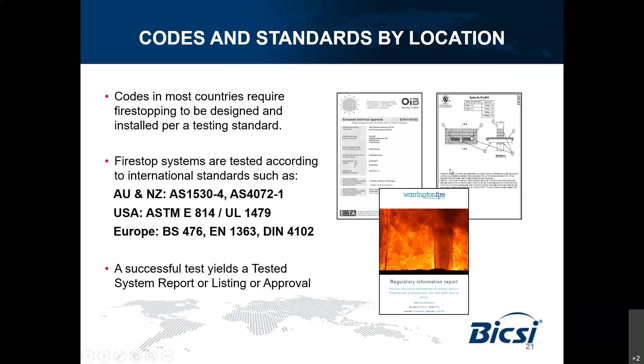Depending on the country, they also have different reporting formats. In Australia, we normally use the bottom reporting format - a tested system report, and the report comprehensively details everything: how it should be installed, what the coverage of this report is, and the designer needs to follow this to specify or install the material. In Europe, they use a different approval layout called ETA, European Technical Approval. In America, they use a certain listing, UL listing, like 2 pages only, but only specific for certain applications.